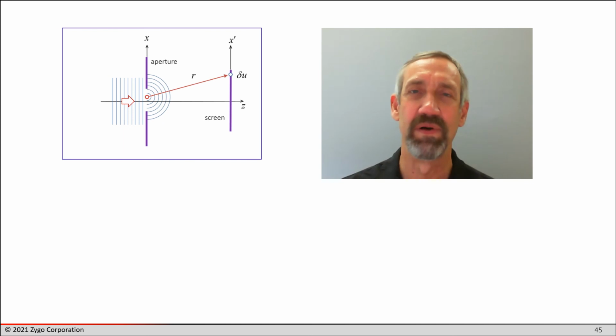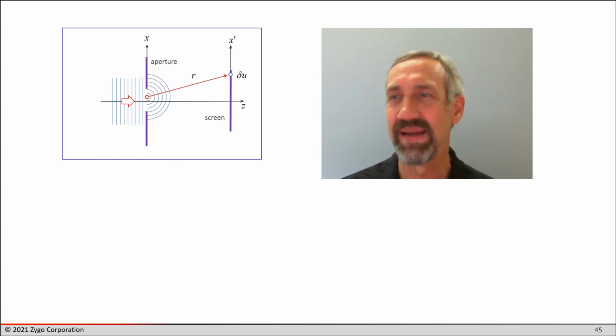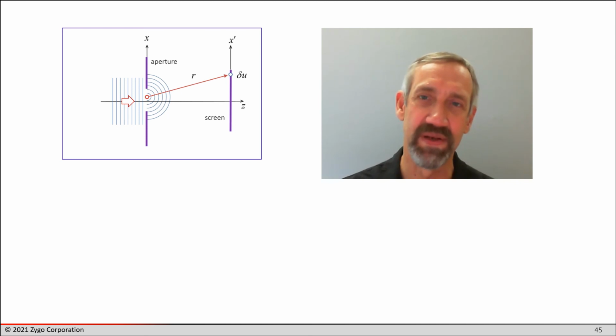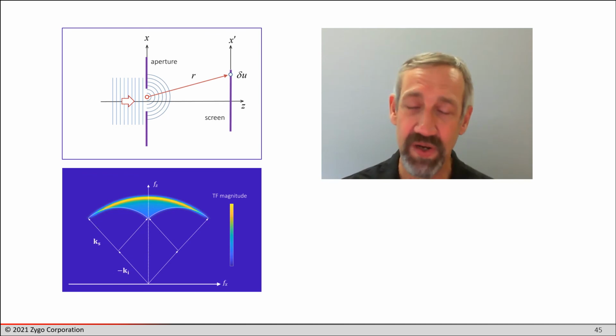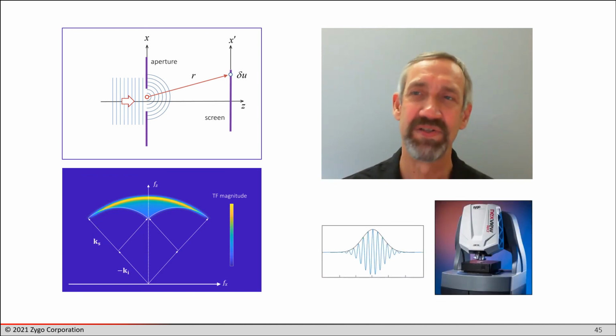A traditional Abbe theory or Fourier optics approach can teach us a lot about how the bandwidth limitations in optical imaging affect a surface topography measurement. That said, another key conclusion of the paper is that at some point we have to take into account the focusing properties of these instruments in 3 dimensions.